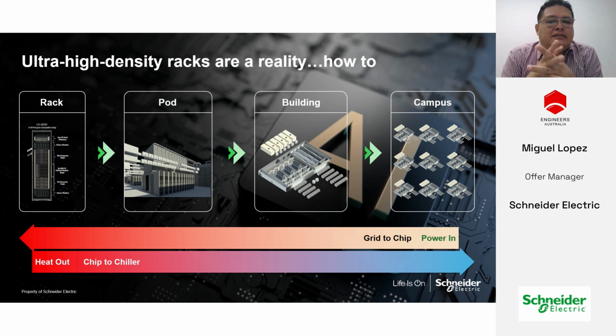These racks are then deployed in so-called pods, which are rows of racks—once again, very familiar to those with experience with air-conditioned racks. Nothing's changed in that form factor. These pods are typically hot-aisle contained, traditionally not cold-aisle contained, which yields more efficiency out of any supplementary cooling, such as in-row coolers.